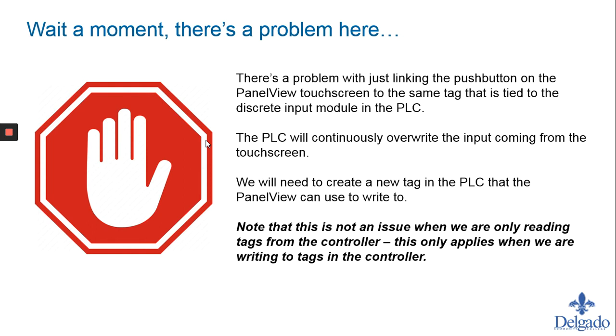The way the PLC does its sweep is that at the top of every sweep, it reads the input table from the physical I/O cards in the rack, and it writes their values. So it's a 0 because I'm not pushing the real push button. Every time it comes to the top of the sweep, it says 0, 0, 0, 0.